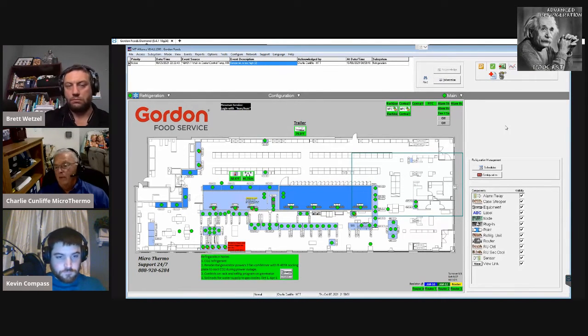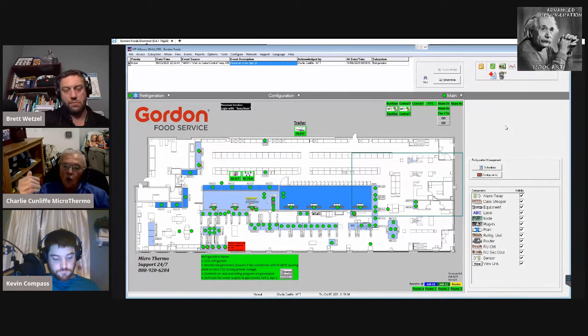So if I have a multi-deck with a case controller and I want it to be smarter, knowing what's happening to the inside relative humidity and inside temperature - if it gets that at a quarter second, a half second, or God forbid one second lag because it's a broadcast network variable, that's not going to foul up the case controller at all if it's a little slow getting that broadcast information.